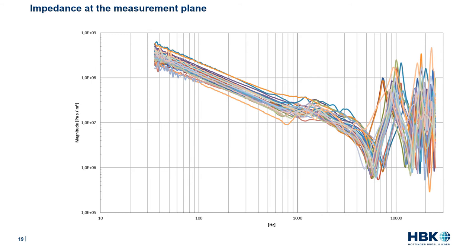In this graph, the impedance at the measurement plane is shown for all 32 subjects. In the raw measurement results, a significant variability in impedance across subjects is noted, especially at frequencies above 3 to 4 kHz where resonances and anti-resonances occur. This variability is due to the variable path length between the measurement plane in the ear canal and the eardrum, and to the large intra-subject variation in ear canal geometries, as well as what goes on in the middle ear.